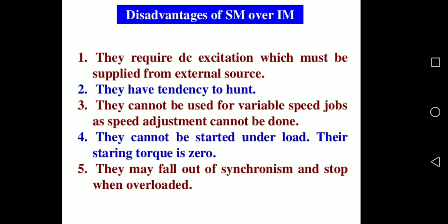Okay. Now coming to the fourth, they cannot be started under load. Their starting torque is zero. Almost most of the machines are started with the load, but only the synchronous machine cannot be started with the load, because the synchronous machine starting torque is zero.